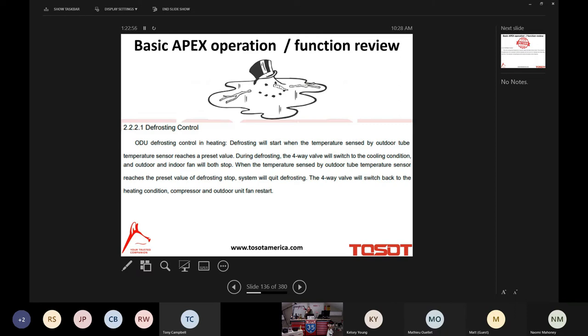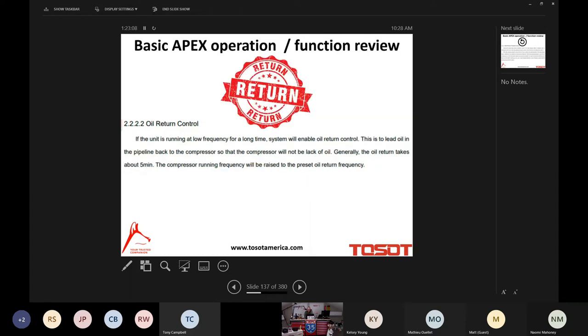Defrosting control. Again, the system will go into a defrost at a preset outdoor air temperature, but it also can be put into a forced defrost if necessary. I'll show you how to do that when we get into troubleshooting. Oil return, I mentioned this when I showed you the flow chart. Again, if the system's been running at low frequency, low RPM, it just wants to ensure that there's no danger that the compressor would be starved of oil, so it goes into that oil return feature.